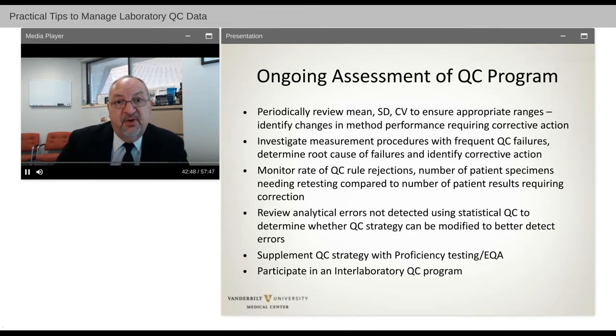Supplement your quality control with external proficiency testing, or EQA, an external quality assurance program. This allows you to participate in inter-laboratory testing, both specimens that have a known value or that you're comparing to your peers, as well as laboratory quality control performance where you have multiple laboratories running the same lot of quality control that you can compare against because they're from the same manufacturer, assays, and analyzers.